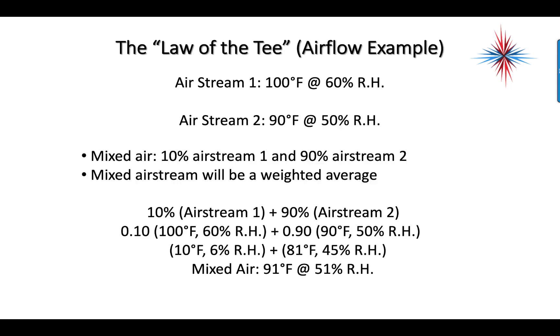That's how we calculate mixed air. Now where does this come into play? Economizers, bypass dampers, coil bypasses. We use it in water all the time in hydronics - mixed water temperatures in boiler loops, mixed water temperatures in domestic hot water supply. So the law of the tee applies to just about everything we do in HVAC whenever we mix two streams of a substance.